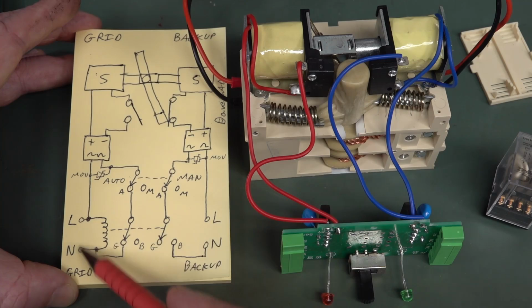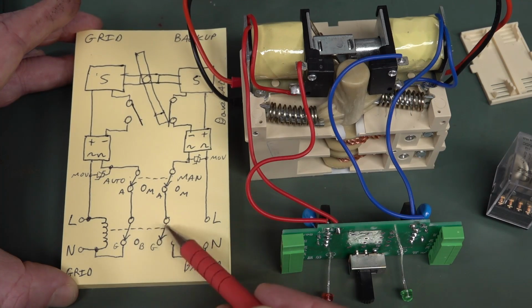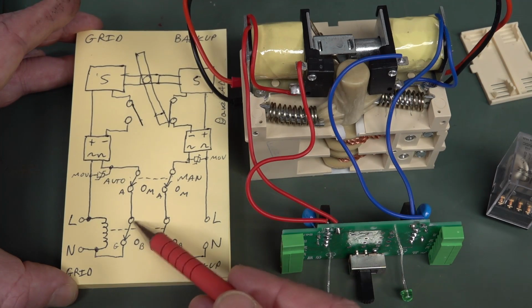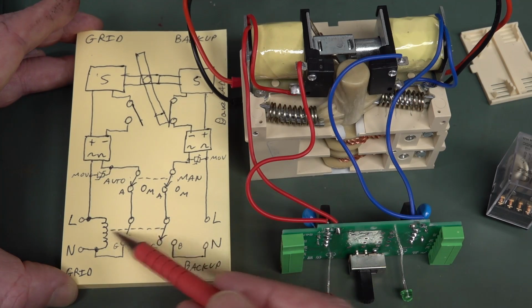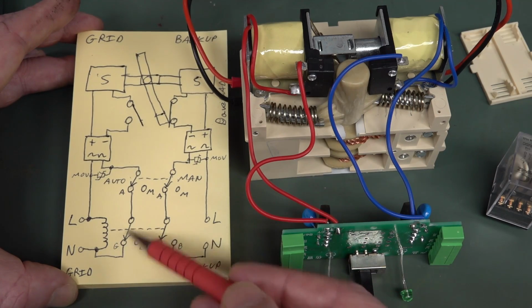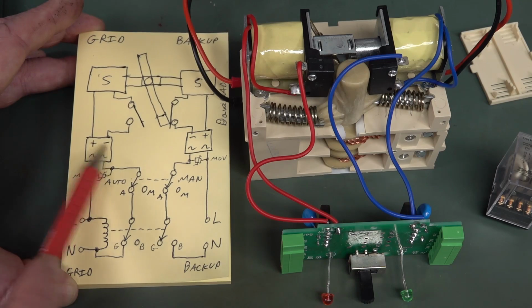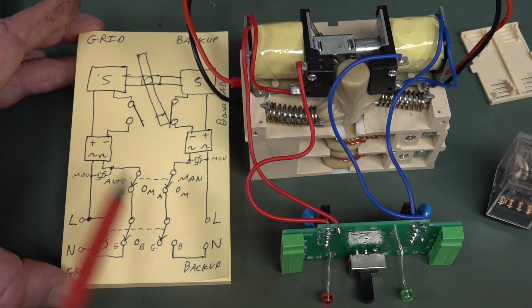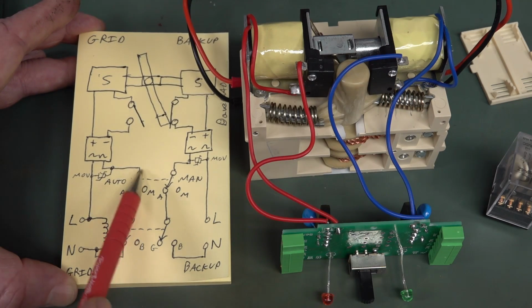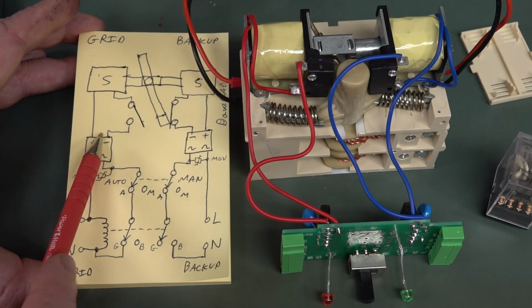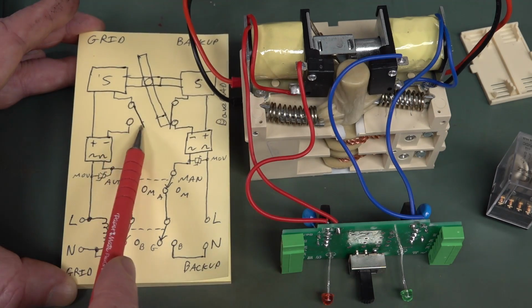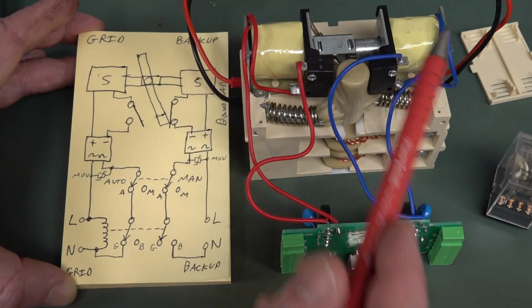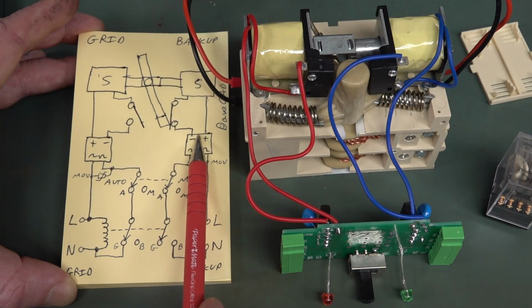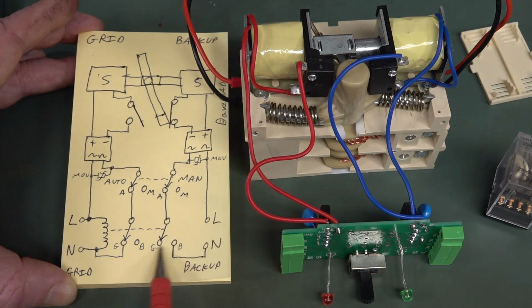So we're assuming that we have got our grid power here, our priority power source is active, and that pulls the contacts. Normally, when you de-energize the relay, it's in the backup position, but when you apply power to the grid, it pulls the contacts this way, and then it's in the grid position like this. So at the moment, the diode bridge here that's powering the solenoid is actually on. You can see it's physically connected through to here, okay? So it's energized, but the micro switch here is disconnected, so the solenoid's not active. And likewise, the backup solenoid here, while it's connected to the diode bridge, is not activated because it's disconnected here, because it's in the grid position, so it's open.